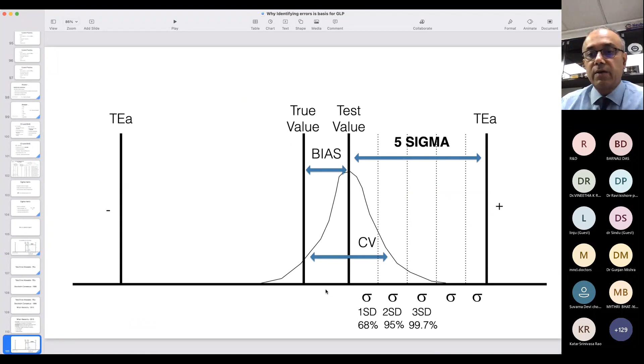So when we look at the distance between the test value and the total error allowable, the number of standard deviations existing will be the sigma number. So if you look at the Milan hierarchy, the clinical outcome TEA, the total error allowable, is so tight that the same CV and bias will give a sigma of 3.5. The second level will give a sigma of 5, and the third level will give a sigma of 7.